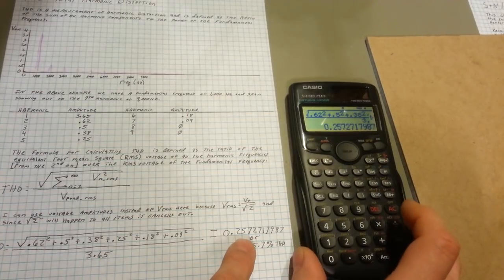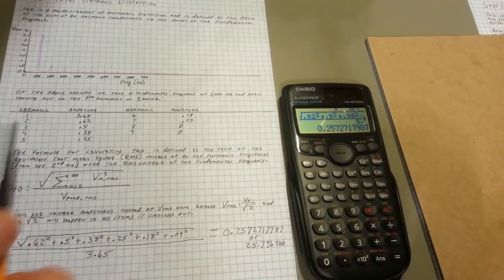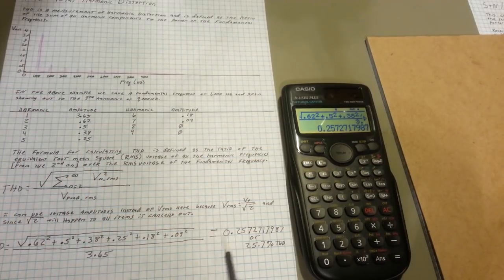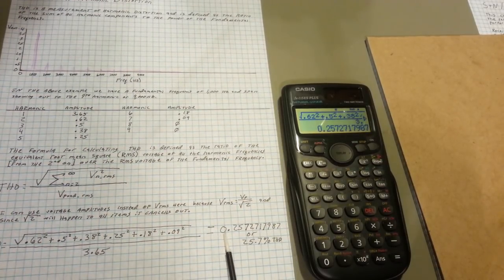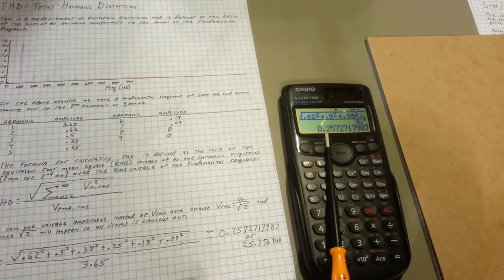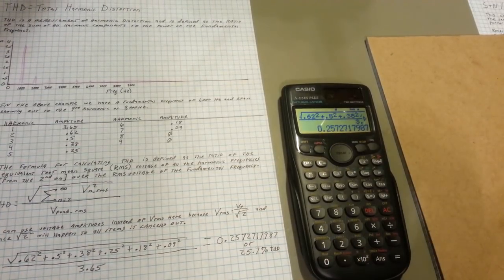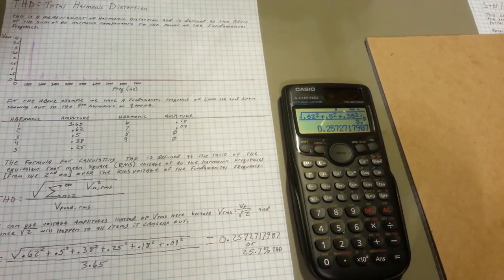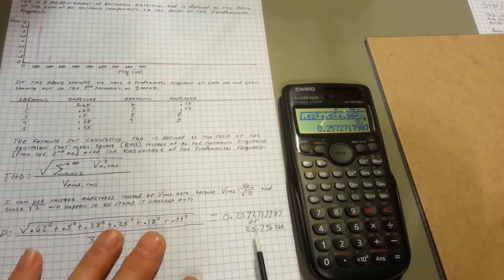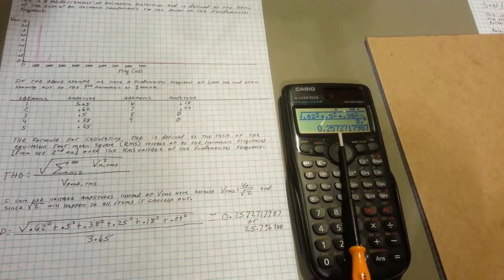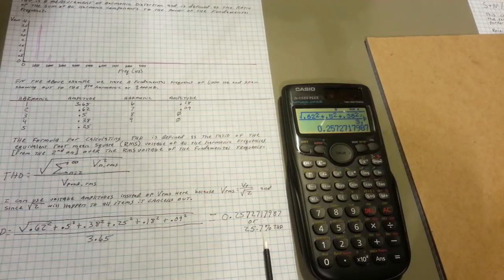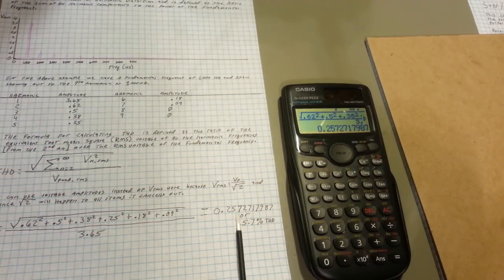and you can see this is absolutely horrible. This is actually horribly distorted. So the calculation comes out to 0.25727, blah, blah, blah, and on probably into infinity. But it just moved the decimal place over 2 places, and that gives you the percentage THD. So 0.257, blah, blah, blah, move the decimal place over 2, gives you 25.7% total harmonic distortion.